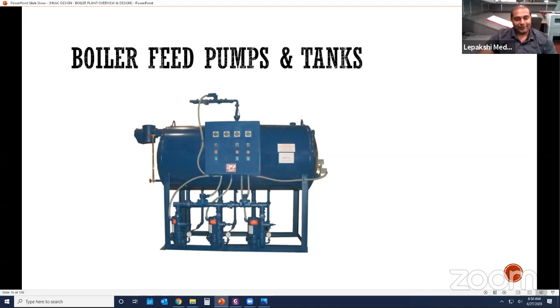You can't have a huge tank over there, right? If it is not necessary, if it is not required, why do you have to put that much size tank? So for every design, it's got to be appropriate. You have to figure out what would be the size of the tank. So that's how you're going to calculate. Once you calculate the loads and all that stuff, you'll come up with BTUs. You convert those BTUs into BHPs, which is boiler horsepowers. Once you know the boiler horsepowers, you will use this formula. For example, I gave you over here, for a 500 horsepower boiler, you have to have a 345 gallon boiler feed tank. It's not an oil tank, it's just water. It's going to supply the water, so it's going to have a reserve of 345 gallons in it. 1 gallon is pretty much 3.8 liters of water. You can do the math and come up with the number.